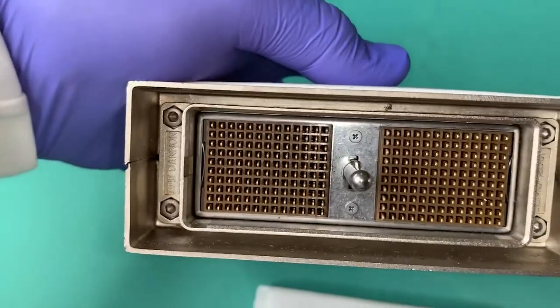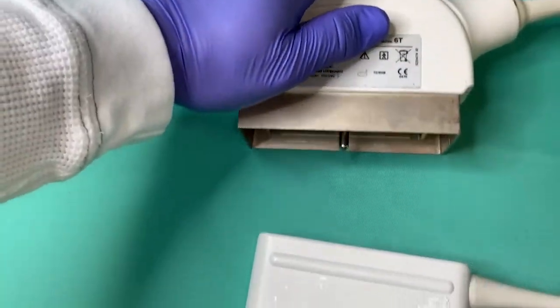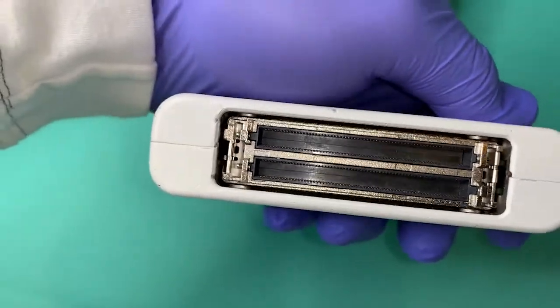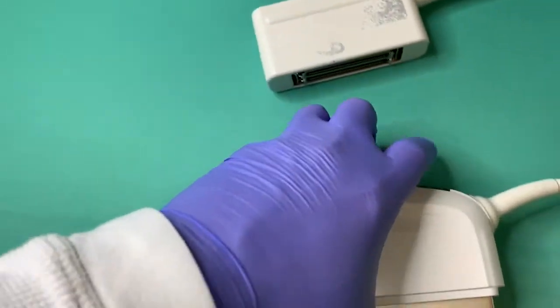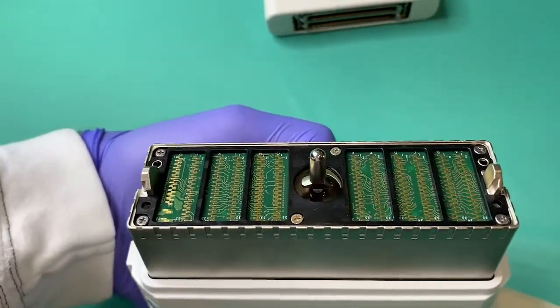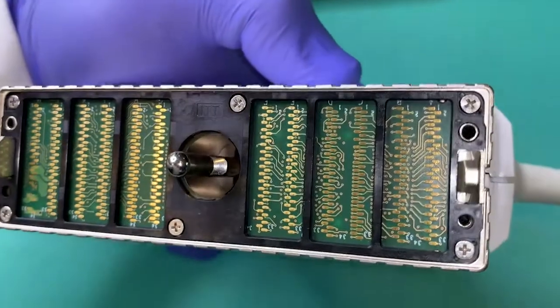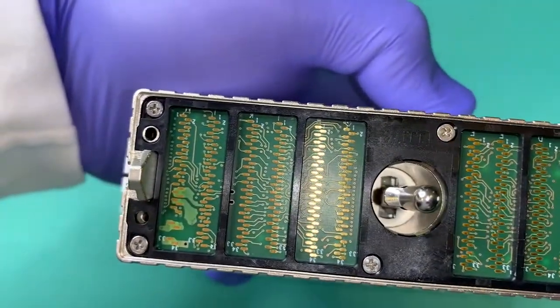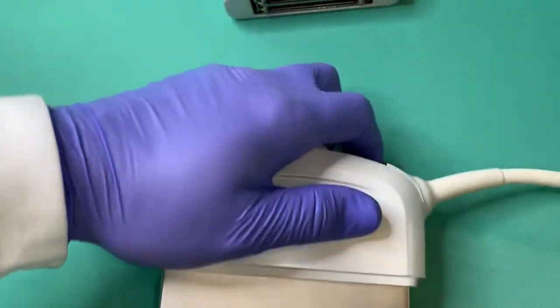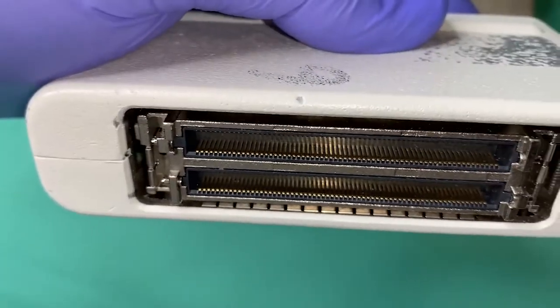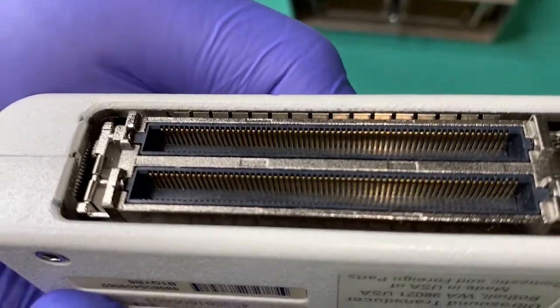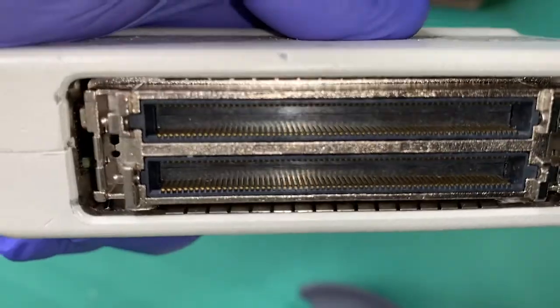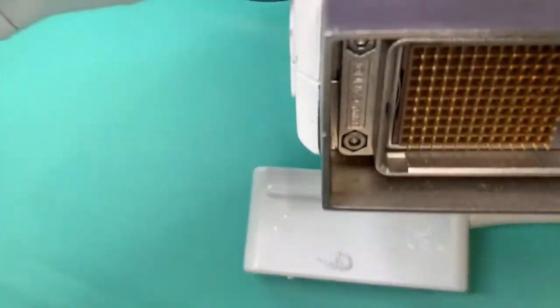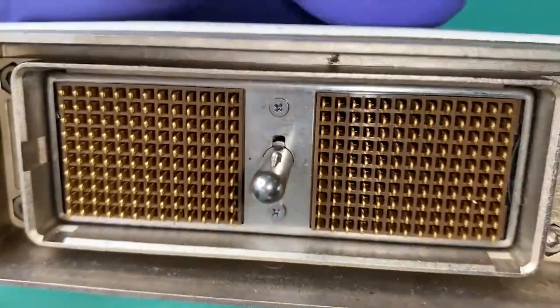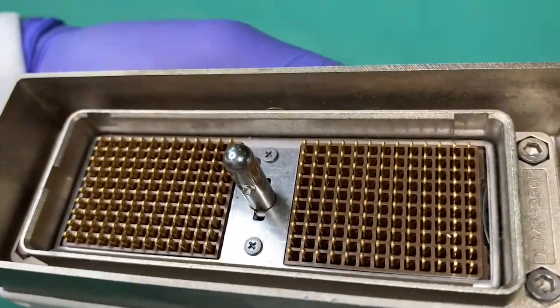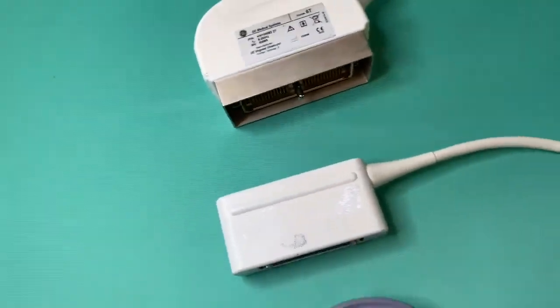Integral to the system connector is the pin bank, which provides the electrical interface to the ultrasound scanner. Certain probe models will have a large system connector with several hundred male pins. Others may have a smaller, low-profile connector with just 2 modular rows of pins, and even other styles may have a flat, pinless surface. Inspect the pin bank under magnification for pins that may be deformed, bent, or crushed. Inspect for areas of white oxidation or green corrosion, which may indicate that the system connector has been exposed to or even splashed with waters or chemical disinfectants.